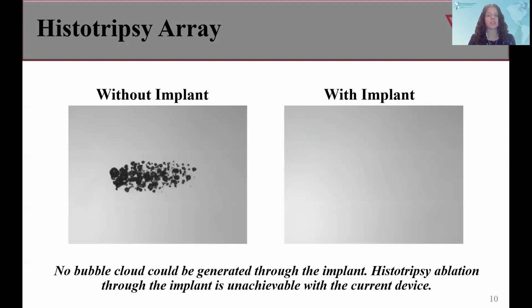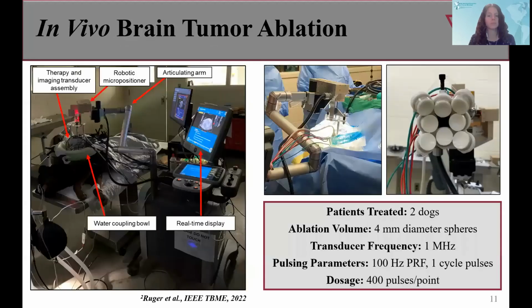Using the current histotripsy device, no bubble cloud could be generated through the implant using this transducer. Tests are ongoing to investigate whether aligning the arrival times of the pressure waveforms from the different histotripsy elements can overcome the attenuation through the implant to generate a bubble cloud to be used for therapy. But for now, the in vivo study was amended to apply histotripsy therapy through an open cranial window using the current system.